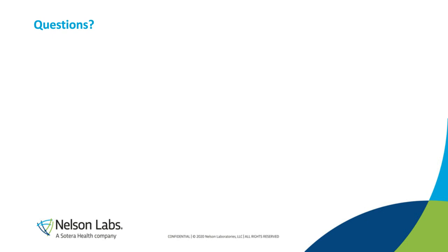Yeah, I'm happy to. So Eva, we monitor these lists ourselves, because we do these screens all the time, and so the legal code inside the MDR. If you go to section 10.4 of the MDR and look there, then there's a code, and it refers to the CLP. And the CMRs are a subset of the CLP list.